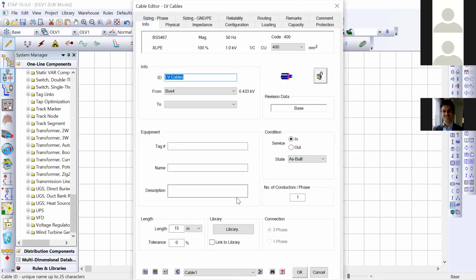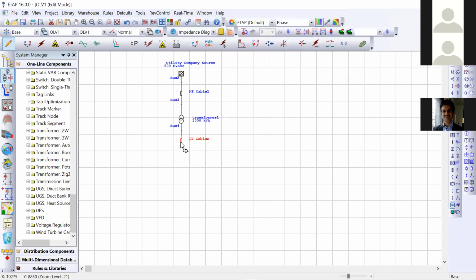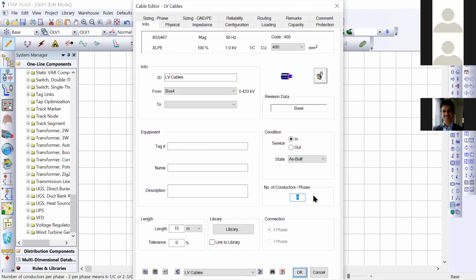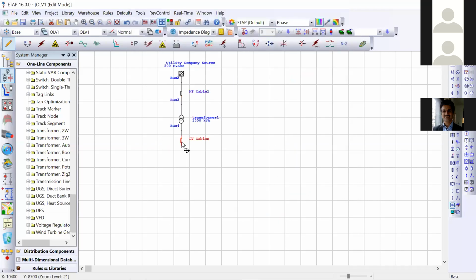but a single cable will not serve the purpose. So we have to take more than 4 cables in parallel from the transformer to the downstream side load. So 4 different cables we have put. Here we have considered 4 cables, and there only 1 cable, because that is the HT cable and this is the LT cables. The ampere rating of a 400 square mm cable is not sufficient to cater to the 1500 kVA rating. That's why we are taking 4 cables. We will verify whether it is suitable or not. We may need to change to 3 or 5. That depends, so we will cross check in our load flow calculations.